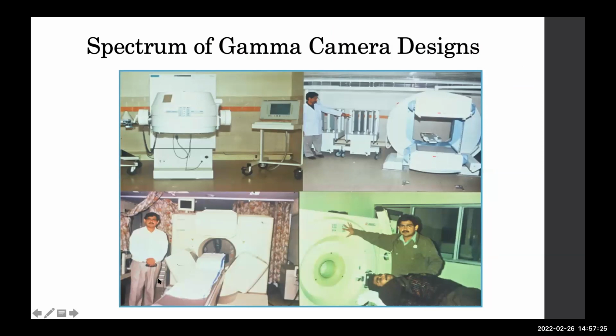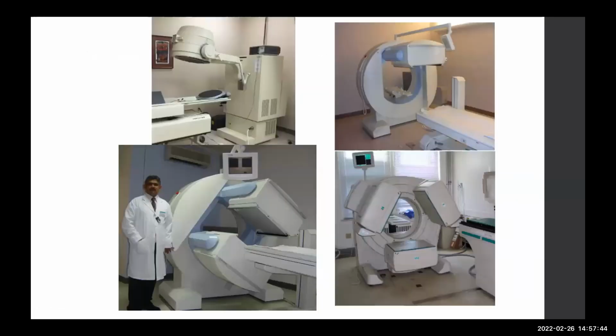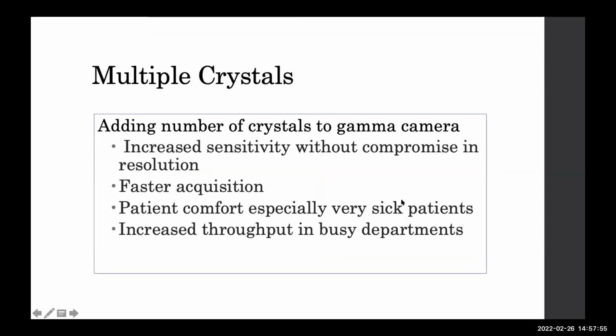Then we had multiple crystal cameras like triple head cameras, and there are ring-like designs, with multiple crystals around the patient in a fixed geometry, and these are commonly used for brain SPECT. You can see only the patient's head can be accommodated. They are used much less often nowadays. Now you can see the single head with the gantry, which can be rotated around. This is a different type which can be rotated, dual head, and this is a triple head camera.